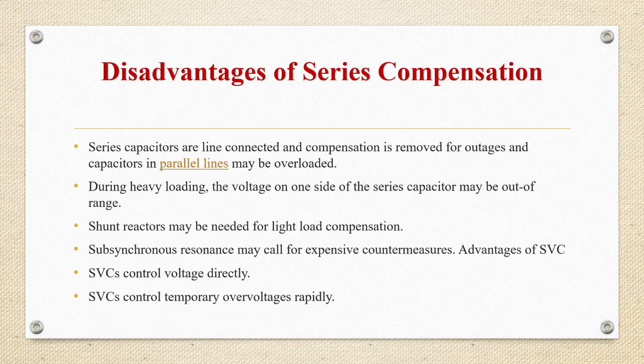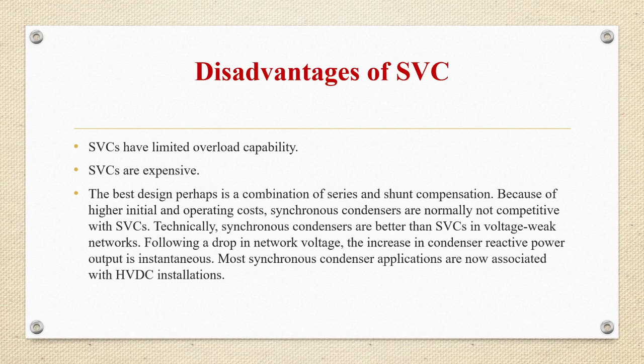So the best design is a combination of series and shunt compensation. Because of higher initial and operating costs, synchronous condensers are normally not competitive with SVCs. However, technically synchronous condensers are better than SVCs in voltage weak networks. Following a drop in network voltage, the increase in condenser reactive power output is instantaneous. Most synchronous condenser applications are now associated with HVDC installations.